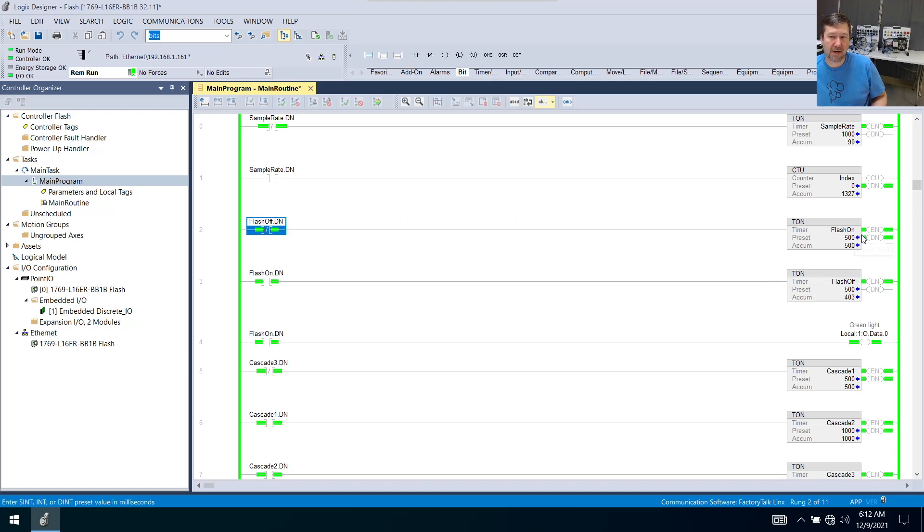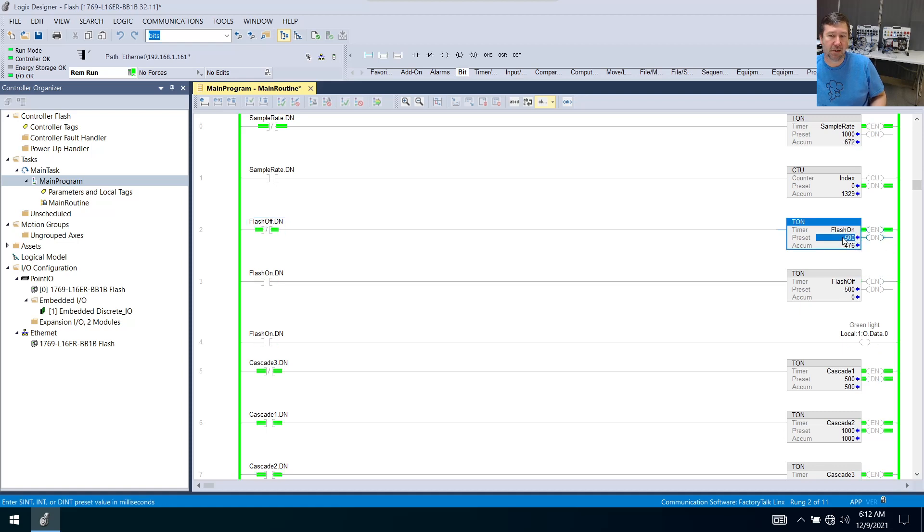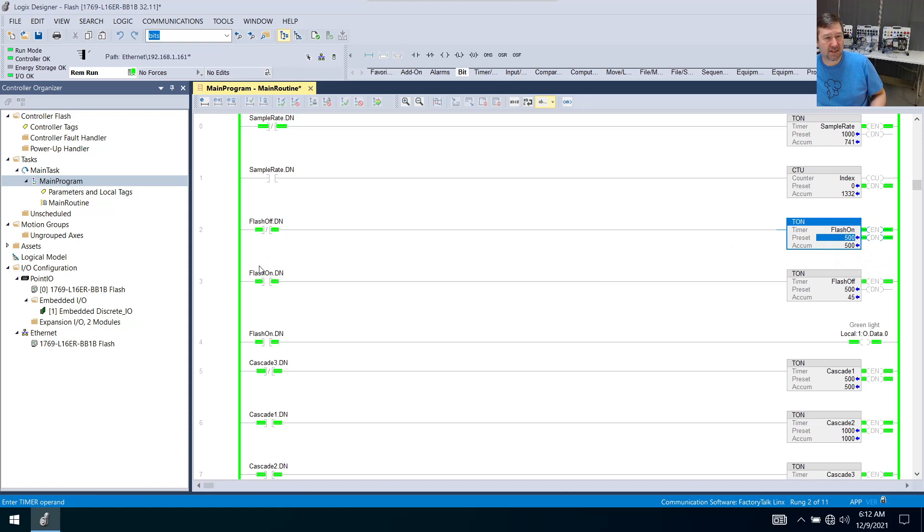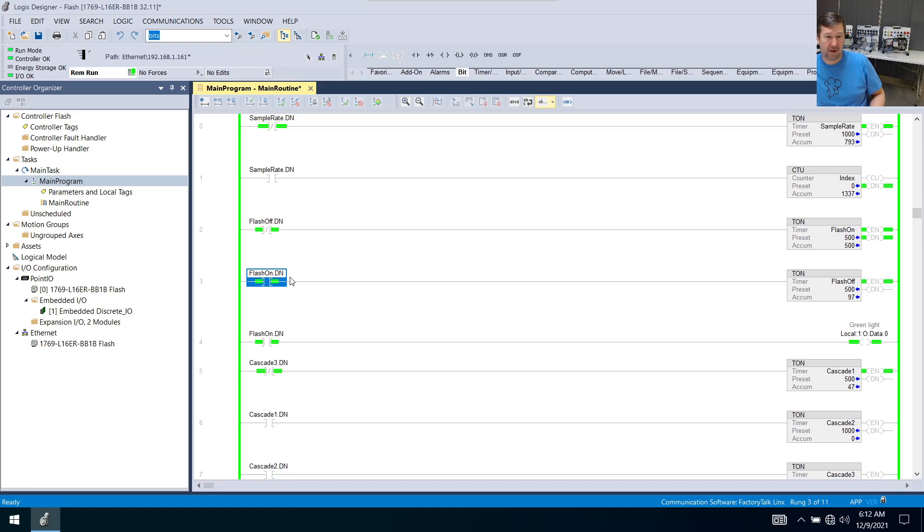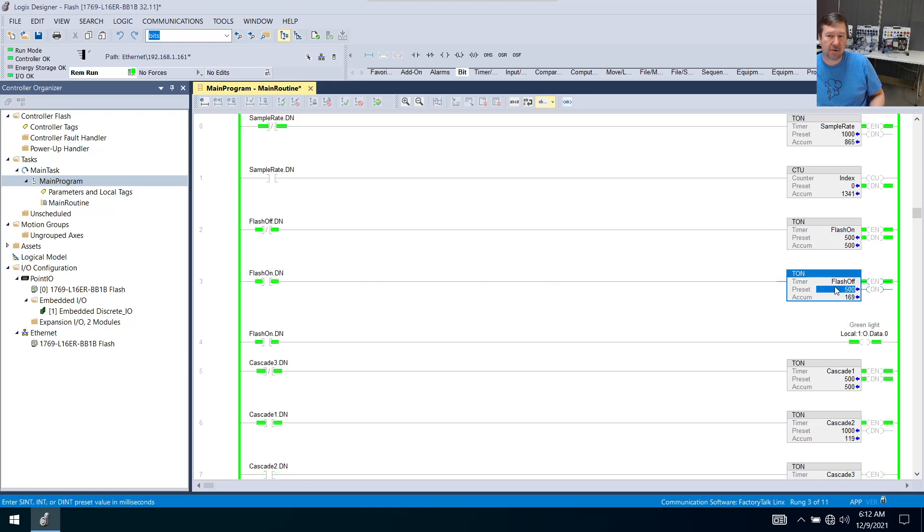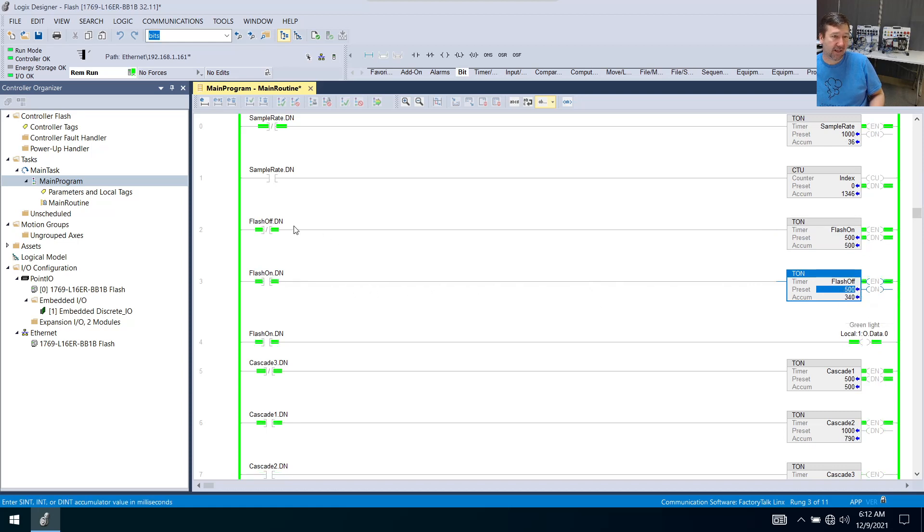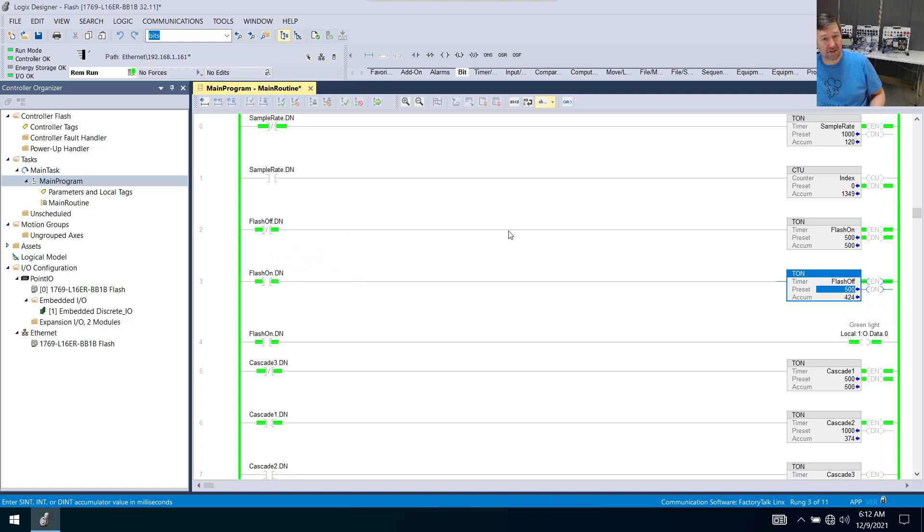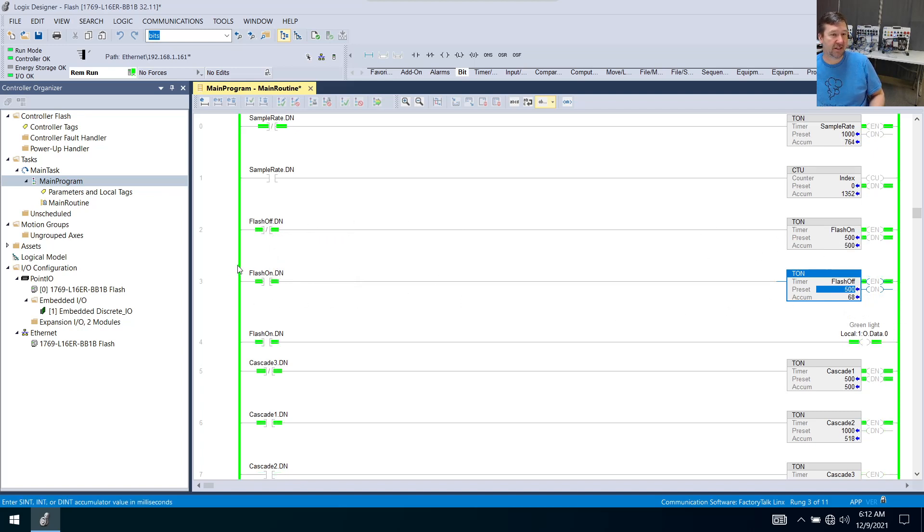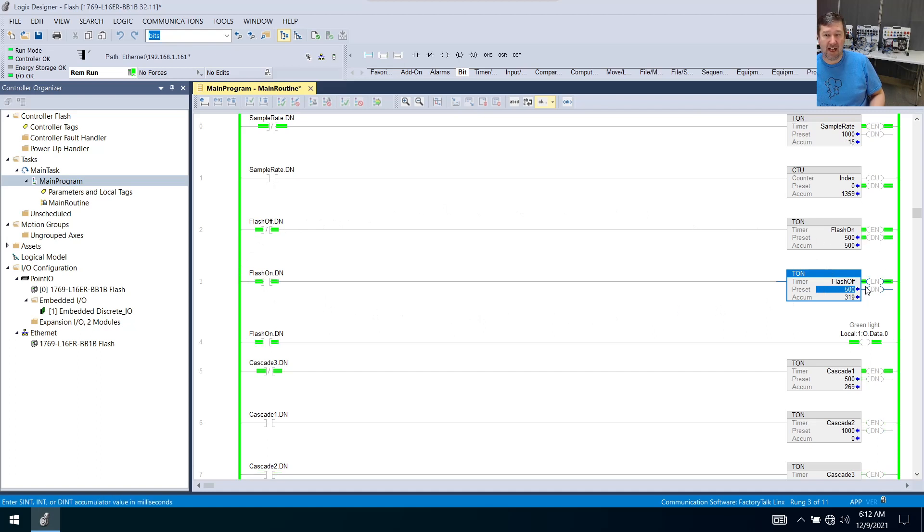it's going to write a zero to everything but the preset value of the flash on, including this done bit right here. So then this was looking for a one, it has zero, it goes false. And that's going to write a zero to everything except the preset in the flash off, including the flash on.dn, which is going to make this true again. And so these two rungs are going to sit there and just alternate back and forth in a half a second increment.